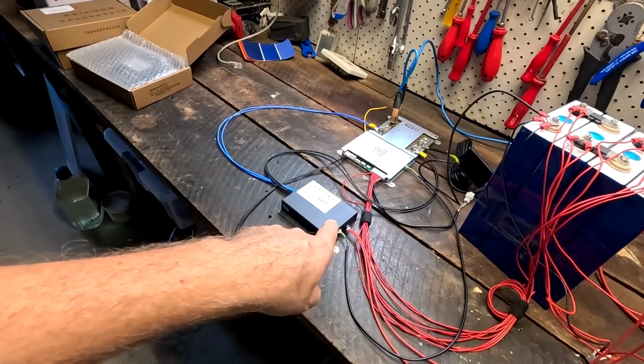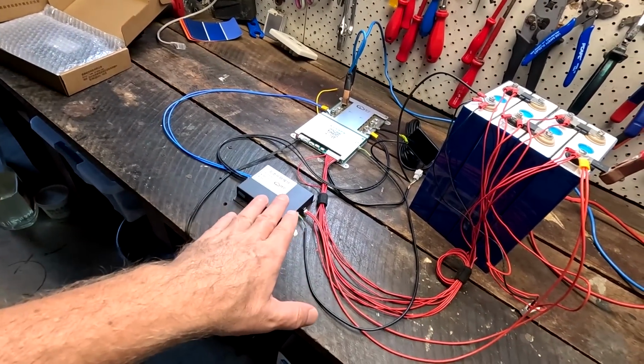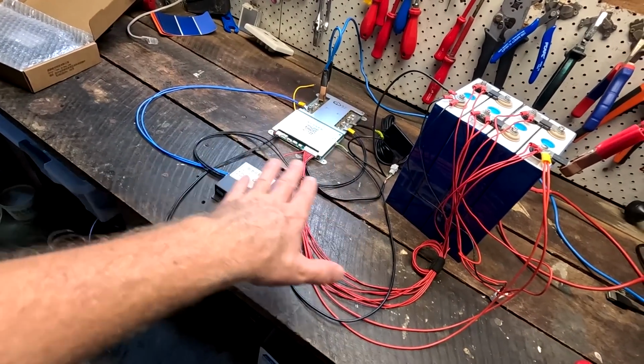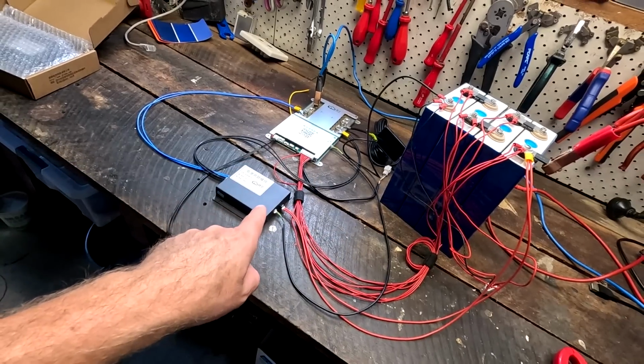So the charge current needs to go under 2.5 amps to turn off the current limiter. I think this is a bit too low, because this would mean the battery is fully charged and the charge current has already tapered off to 2.5 amps. The other situation where the charge current drops under 2.5 amps is in the afternoon when the sun goes down. So once this current limiter is activated, it stays activated until the current going into the battery goes under 2.5 amps.